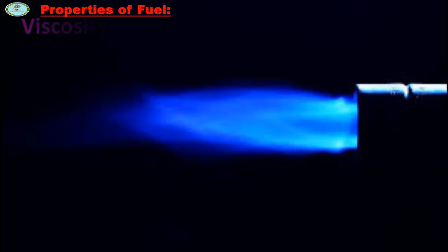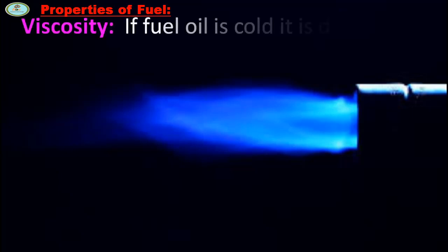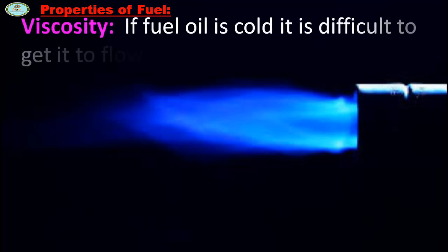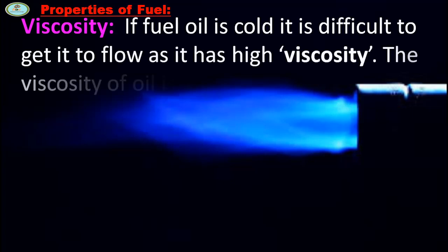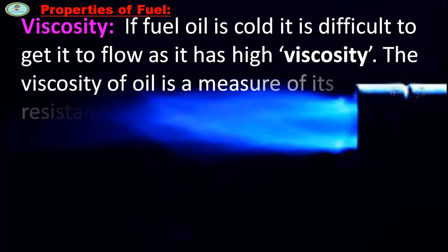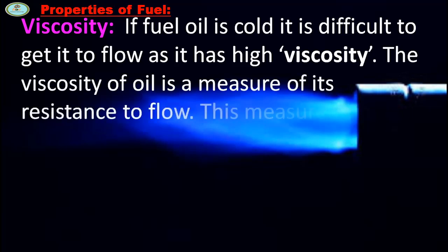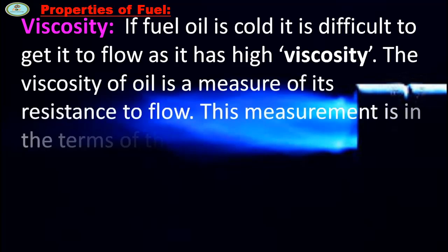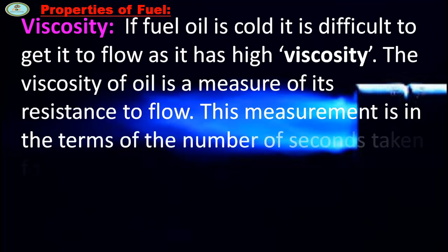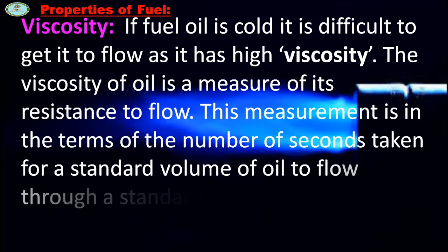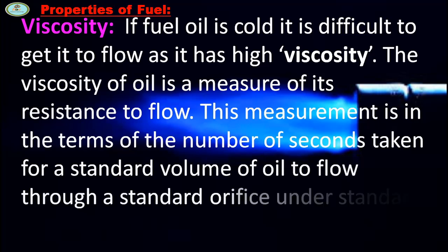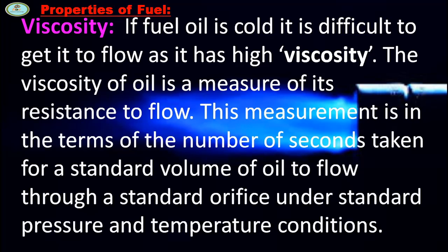Properties of fuel. Viscosity. If fuel oil is cold, it is difficult to get it to flow as it has a high viscosity. The viscosity of oil is a measure of its resistance to flow. This measurement is in terms of the number of seconds taken by a standard volume of oil to flow through a standard orifice under standard pressure and temperature conditions.